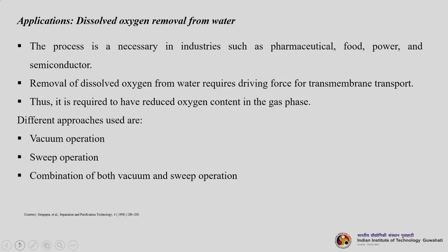Another application is dissolved oxygen removal from water. This is a very important application in industries such as pharmaceutical, food, power and semiconductor. You need to remove the dissolved oxygen from water. Removal of dissolved oxygen from water requires a driving force for transmembrane transport. Thus, it is required to have a reduced oxygen content in the gas phase. Different approaches are used. You can have a vacuumized operation, you can use a sweep gas based operation, or you can use both vacuum and sweep together.